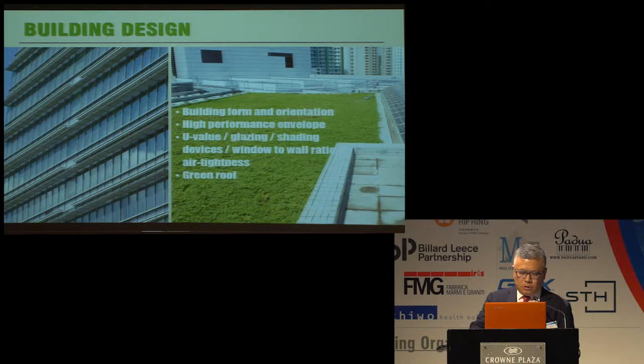Now, the architect and building services engineer can also work together to optimize the design of the building envelope to maximize its thermal performance. The building shape, volume, and orientation will have an impact on daylighting, solar heat gain, heat loss and energy consumption. We should be using building materials with low U value and emissivity for the opaque envelope components, such as the walls and roofs, and minimize the amount of glazing and select glass with low U value and solar heat gain coefficient. Provide external shading devices such as fins and overhangs.